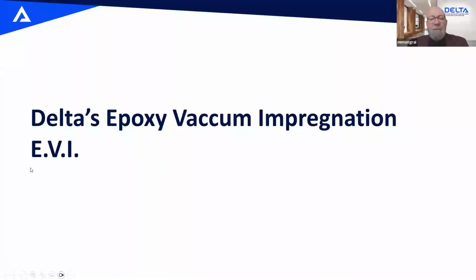I'll talk a little bit later about the bidirectional thing. Is there a significant difference between a four or five-legged core? Yeah, the difference will be mainly in the size of the core itself, and it's going to be the price. So mainly a five-legged core. Let's say you start with a three-legged core. If you go to a four-legged core, you have 25% more material, and with a five-legged core, you have 66% more material. So it's a big impact on the cost. Again, it depends if you go with copper or aluminum windings, but you can figure, as a rule of thumb, four-legged core versus three-legged core, you may talk 20% more. If you talk five-legged core versus three-legged core, you may talk 40, 45% more money, more or less.